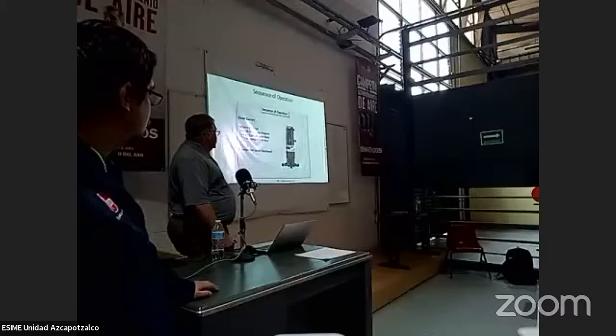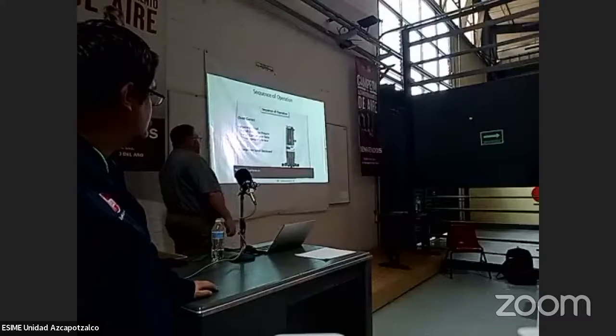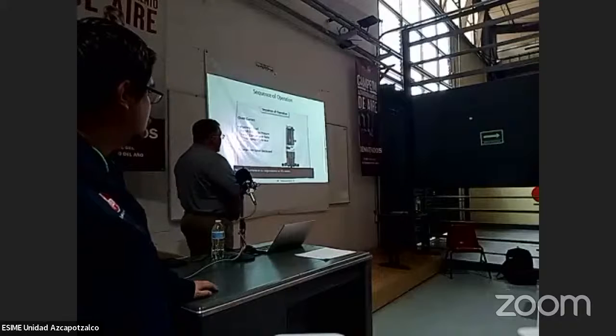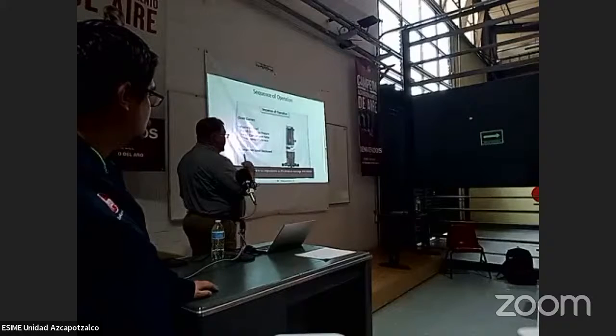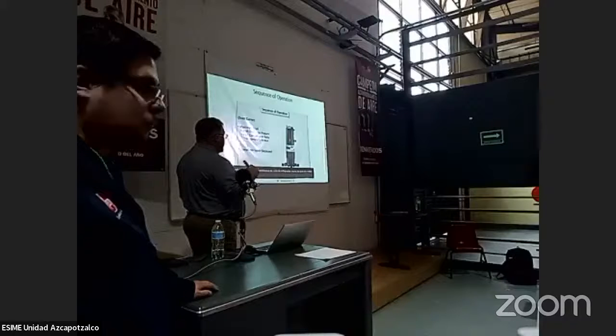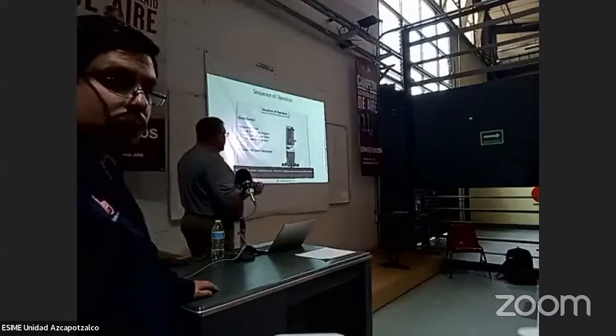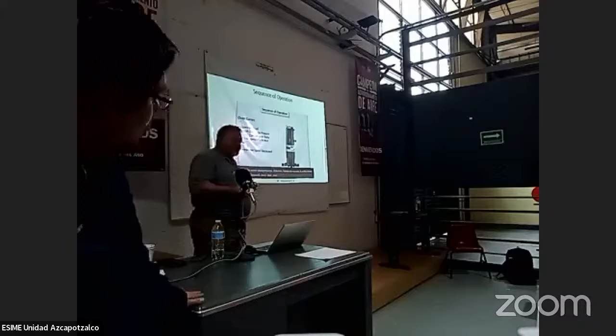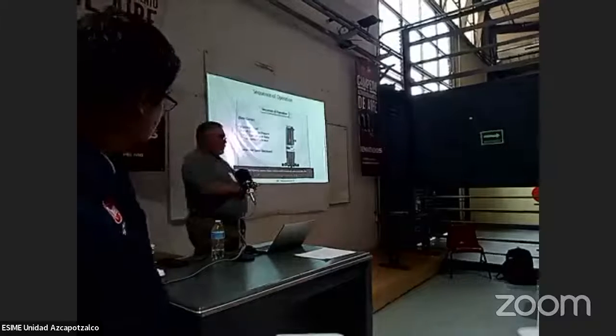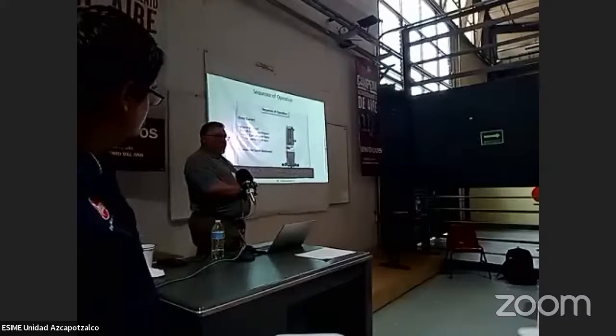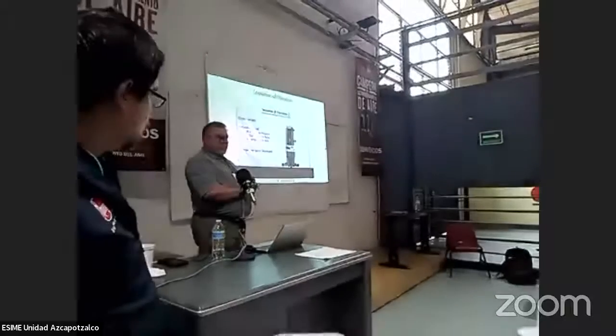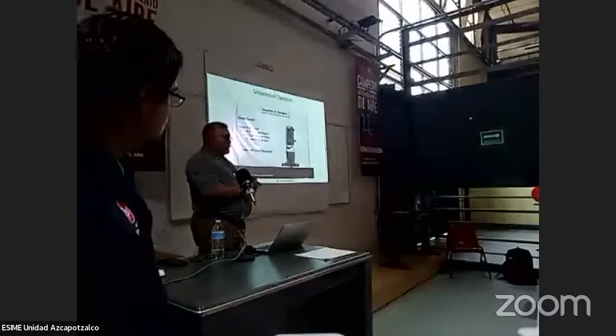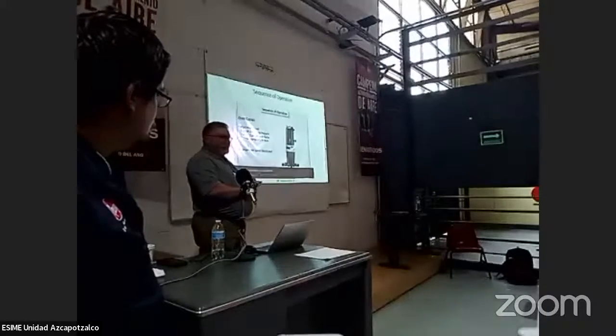So overcurrent on the maximum, your high discharge pressure, high compression ratio, is what's going to cause the overcurrent protection. So when that happens, the compressor speed will decrease. Now, what can cause high discharge pressure? Overcharge. Dirty condenser coil, right? Fan motor not operating properly.